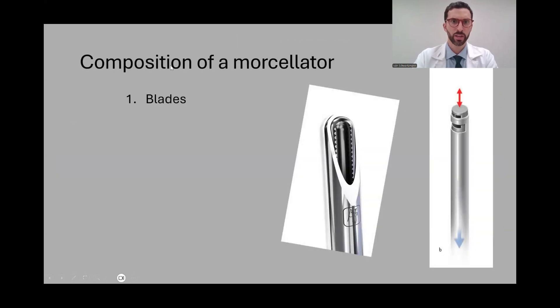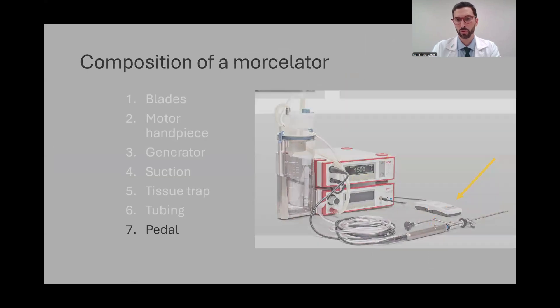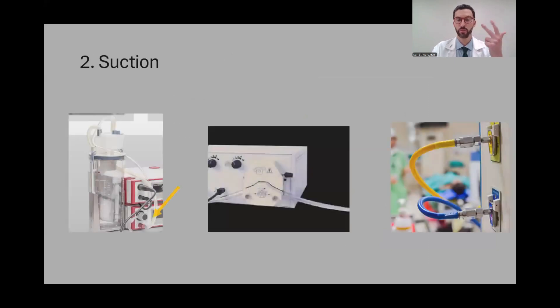The composition of a morcellator is quite complex. Morselators are composed of many different pieces, but most of them vary in one of two things: the blades and the suction system. The blades can be oscillating, moving from one side to the other, or reciprocating, moving from the front to the back.